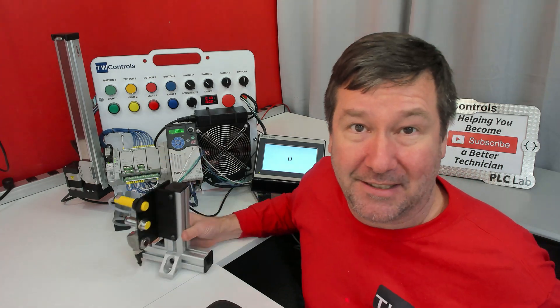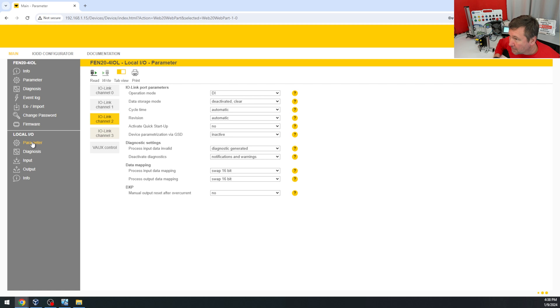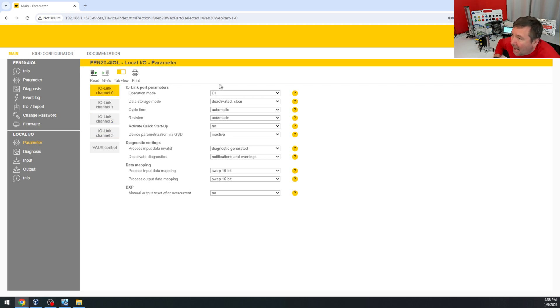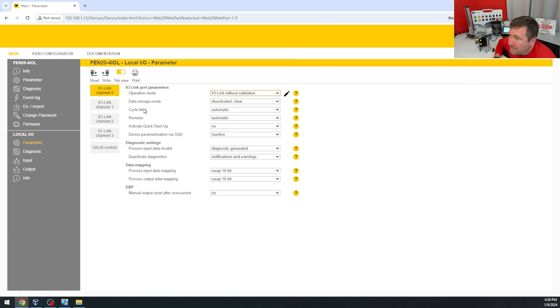So we're going to go to our local IO parameters, and we're going to select channel zero, and right here, the default configuration is DI. We're going to select IO link without validation, and click the write button.